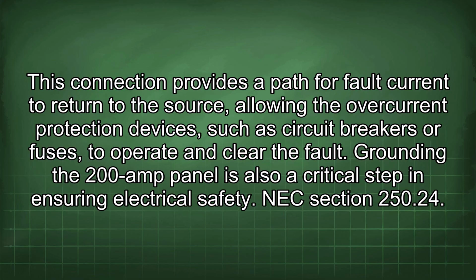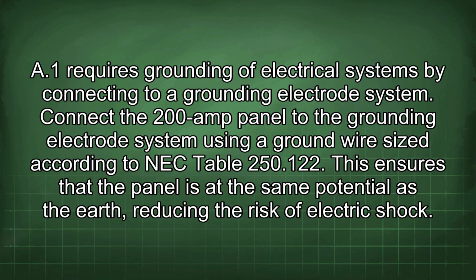Grounding the 200 amp panel is also a critical step in ensuring electrical safety. NEC Section 250.24 A1 requires grounding of electrical systems by connecting to a grounding electrode system. Connect the 200 amp panel to the grounding electrode system using a ground wire sized according to NEC Table 250.122. This ensures that the panel is at the same potential as the earth, reducing the risk of electric shock.